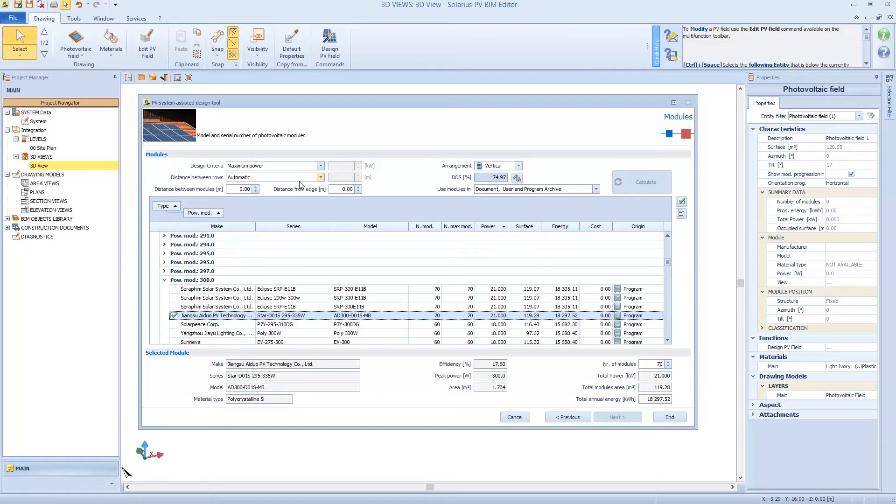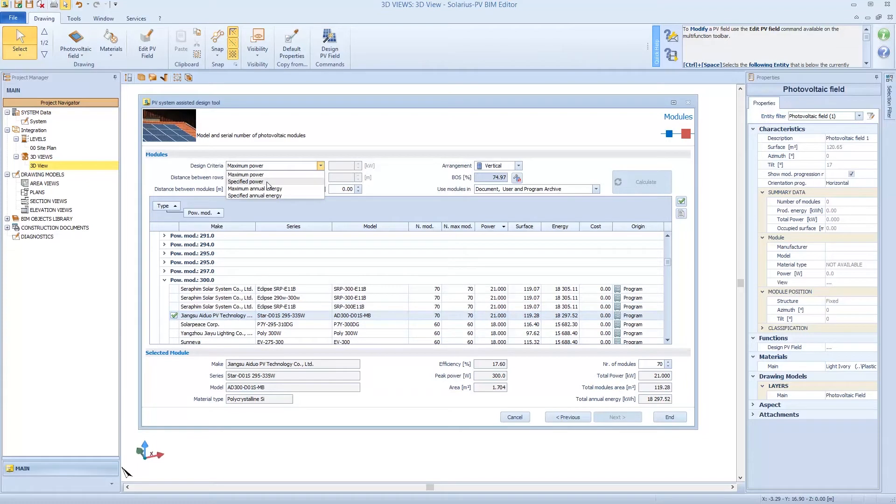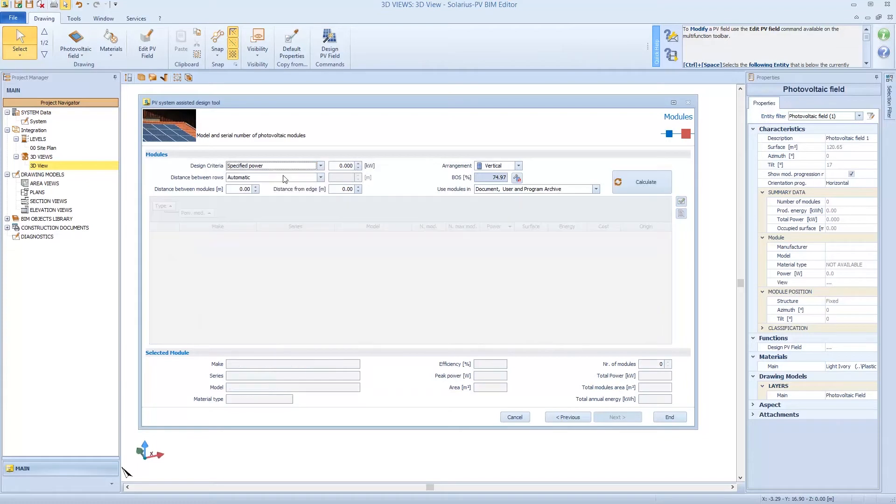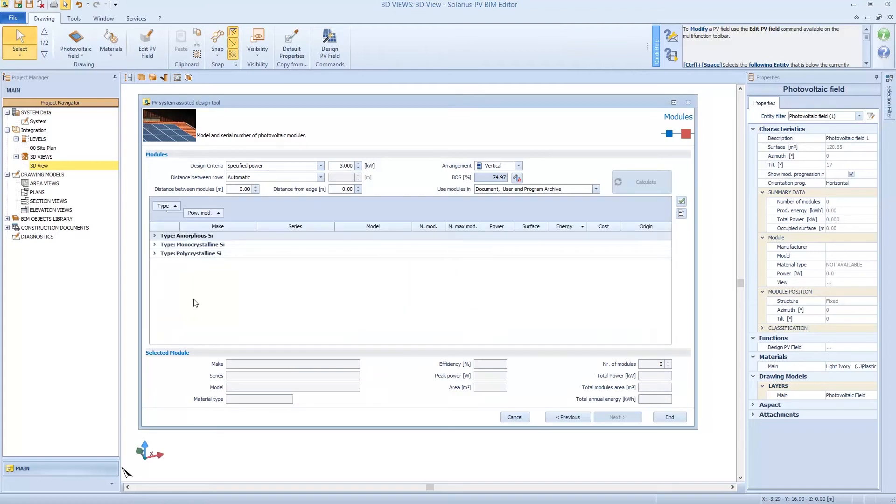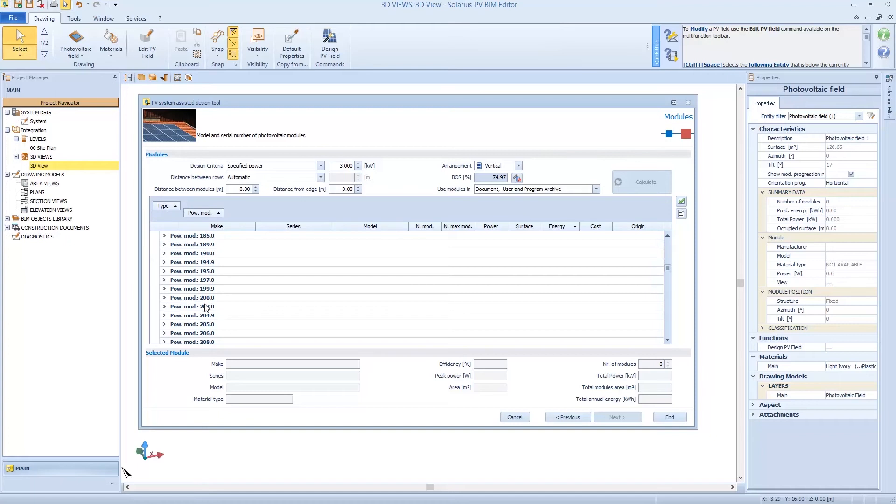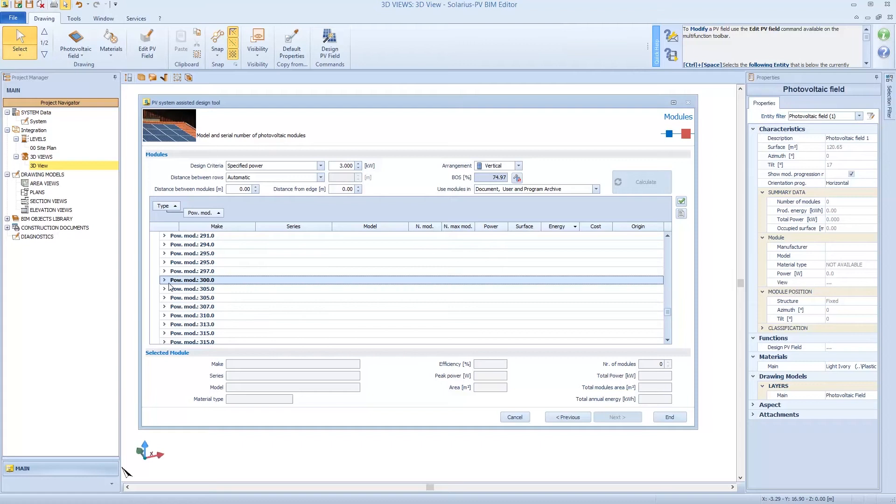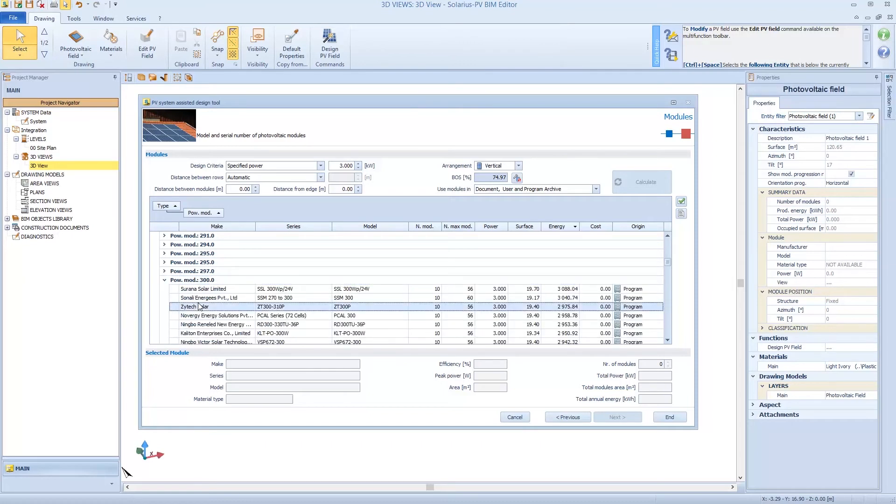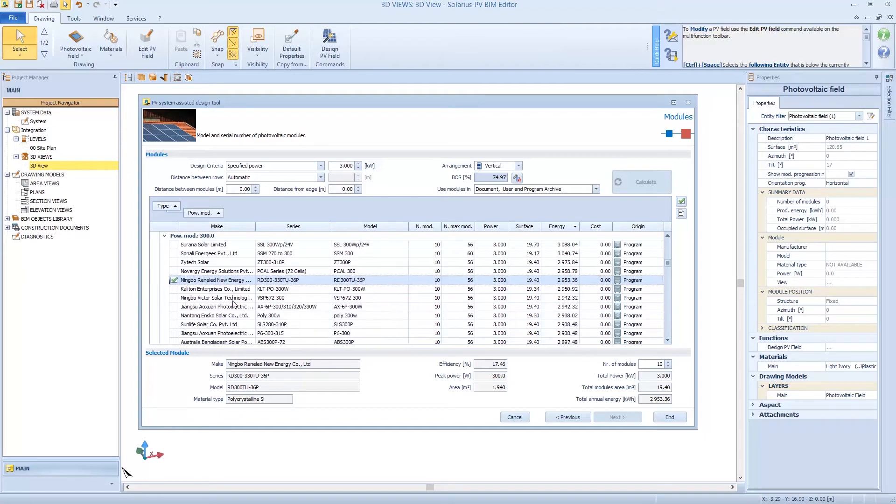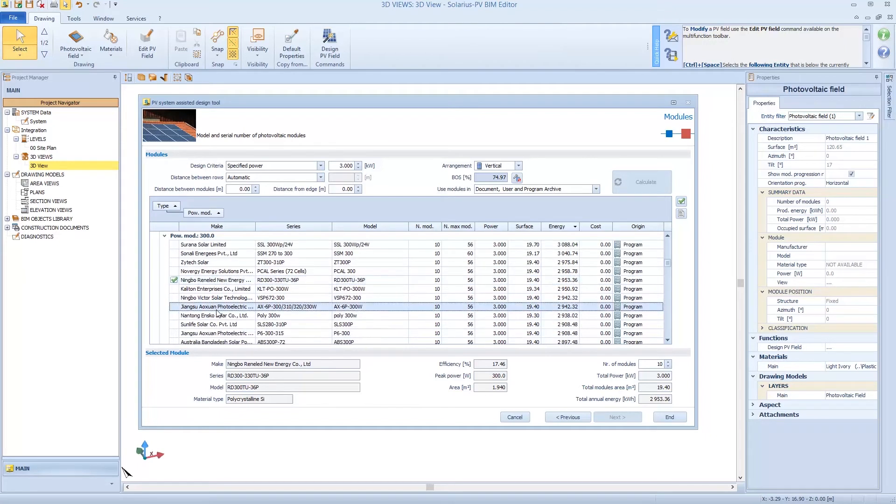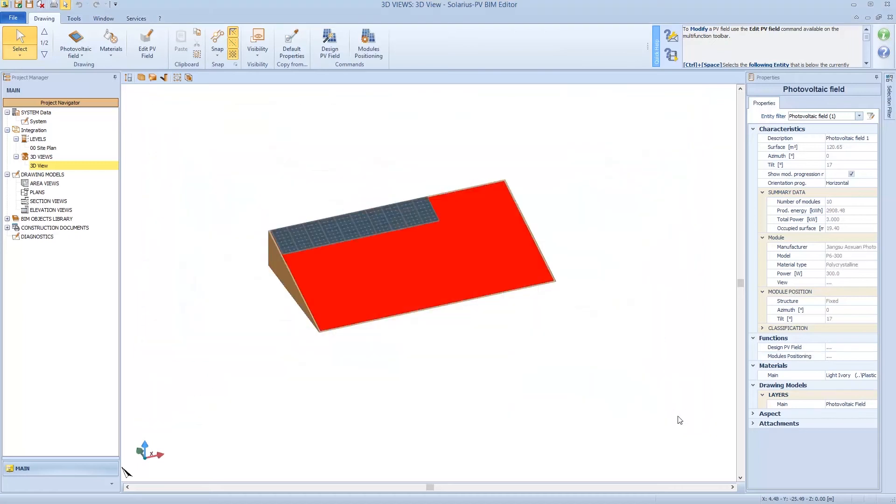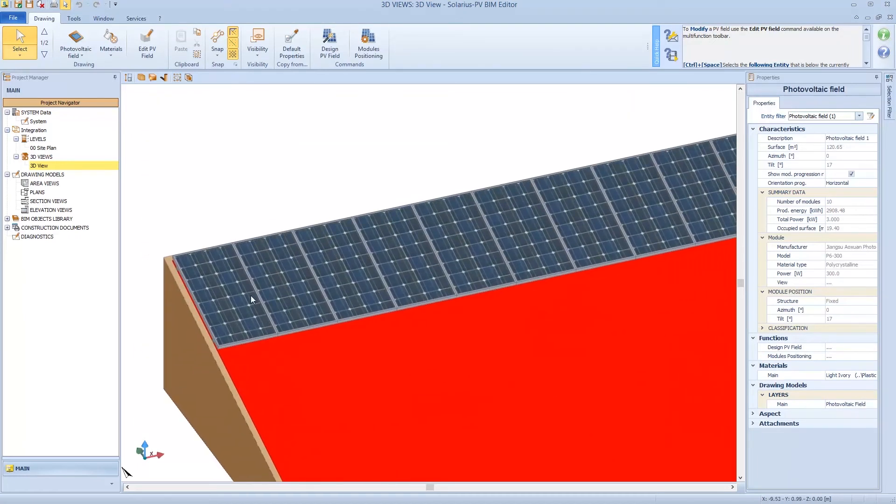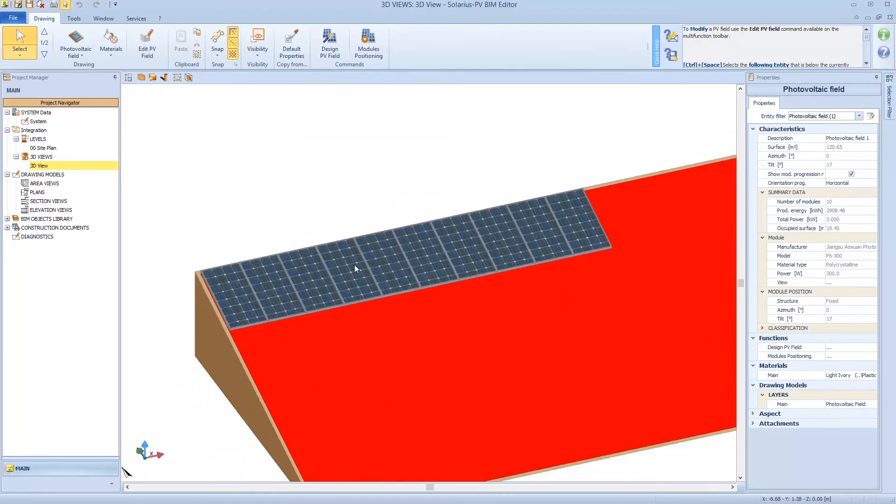Instead, if I want to design a specific power, 3 kW for example. We calculate again, we interrogate the archive and choose modules of 300W. So what's happening? Now we obtain 10 modules. And this is according to our design criteria. So we click on End, Solarius positioned the modules on the 3D view.